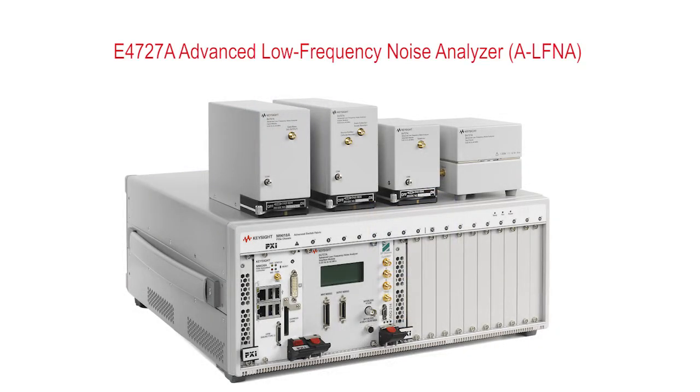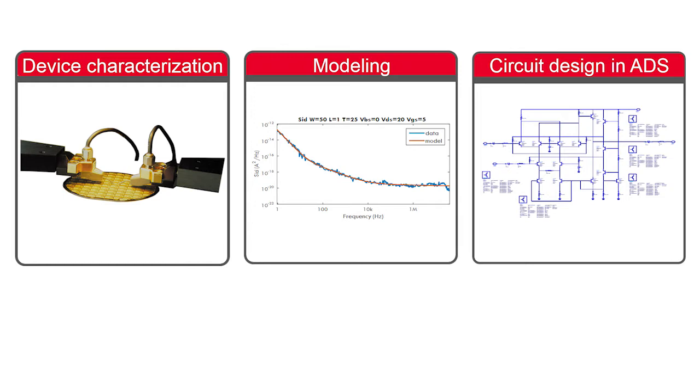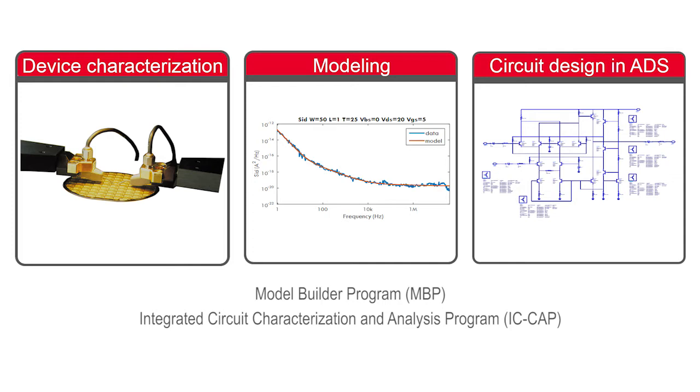The E4727A advanced low-frequency noise analyzer enables a closer, deeper look at noise. A device designer or characterization engineer may extract noise models using powerful device modeling software like the device model builder MBP or the integrated circuit characterization analysis program ICCAP. The models can be used by circuit designers to push the envelope in low-frequency circuitry.